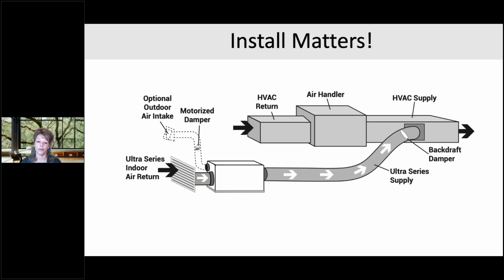We get calls, we get homeowners that are upset, we get HVAC contractors that are frustrated because they installed a dehumidifier, but it wasn't installed correctly. So we want to make sure as much as possible that we pull from a dedicated return to the dehumidifier and tie in to the supply of the HVAC system. This allows us to lock out the AC and the dehumidifier from running at the same time. So maybe our strategy is we allow the AC to come on, run till it hits that temperature set point. When the air handler shuts off, and the RH is still too high, the dehumidifier comes on and dehumidifies. This also minimizes a lot of static issues with the HVAC and the dehumidifier together.